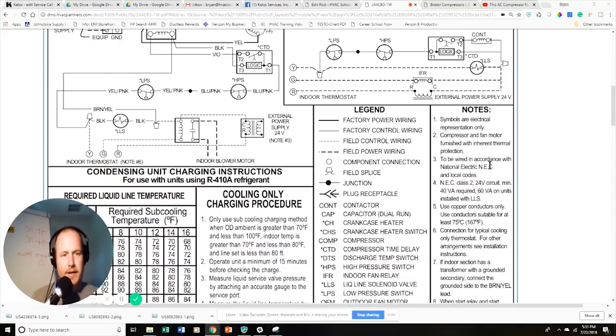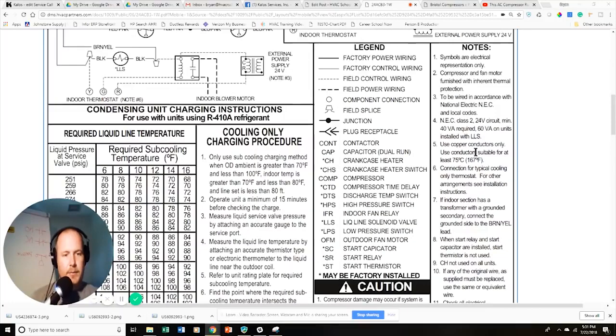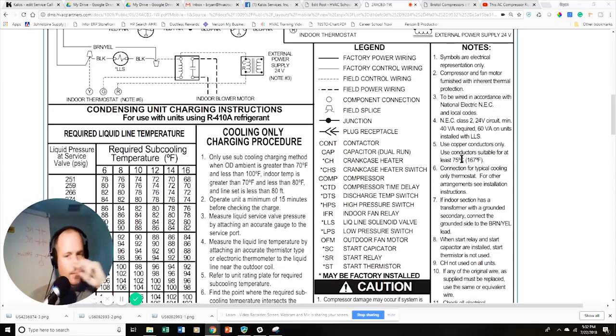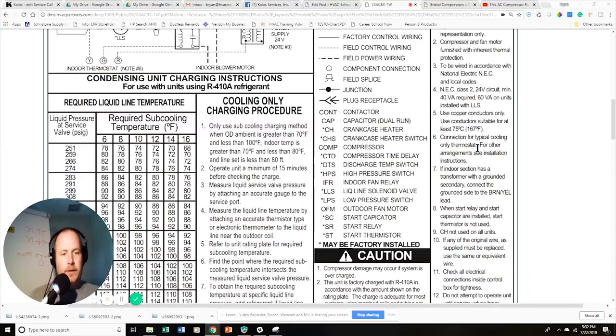The diagram also refers to the NEC — everything you wire in needs to be in accordance with the NEC and local codes. Use copper conductors only, and use conductors suitable for at least 75 degrees Celsius. That's interesting because it excludes Romex — NM non-metallic cable — which is only rated at 60 degrees Celsius. So technically you should not be using Romex to wire in this particular unit.